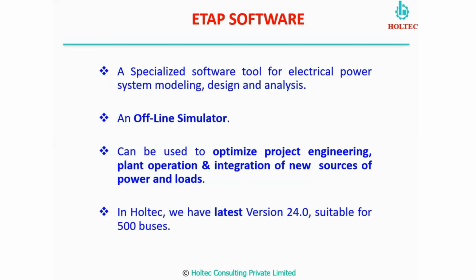This is an offline simulator. What does it mean by offline simulator? We can model the power distribution system in ETAP software. We can simulate any kind of situation in your power distribution, like any fault, any overloading, any sort of operation, and we can check the results of those changes or inputs we have simulated in the model. So we can get the outputs, and with the help of those outputs, we can analyze and conclude what exactly will be the requirement for our power distribution system to take care.